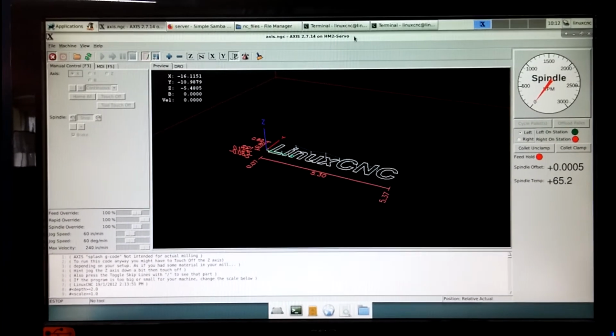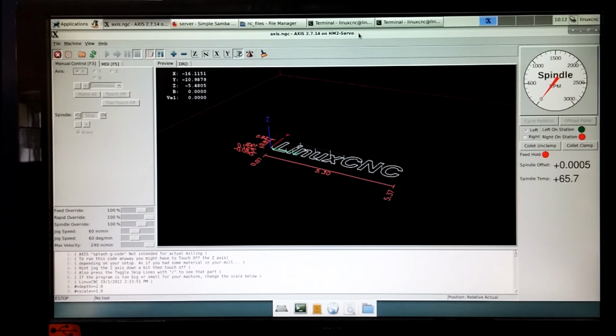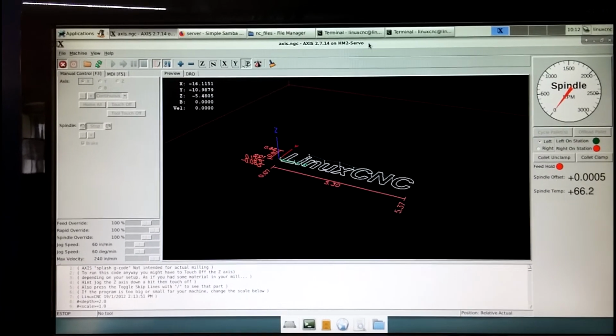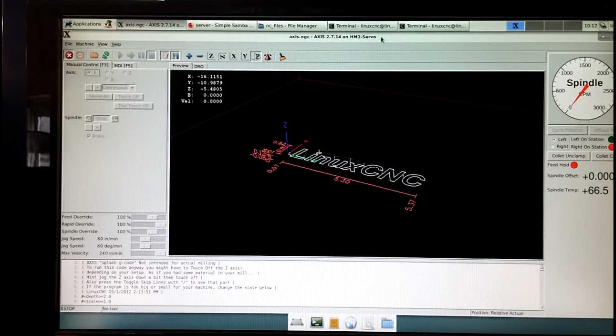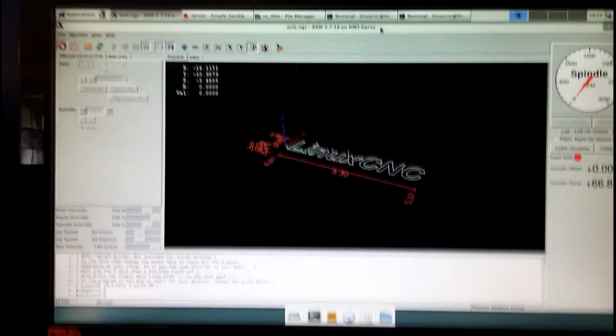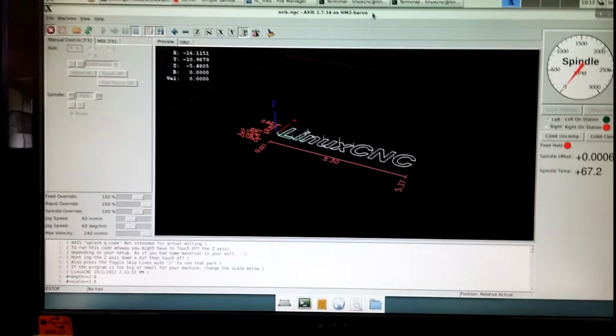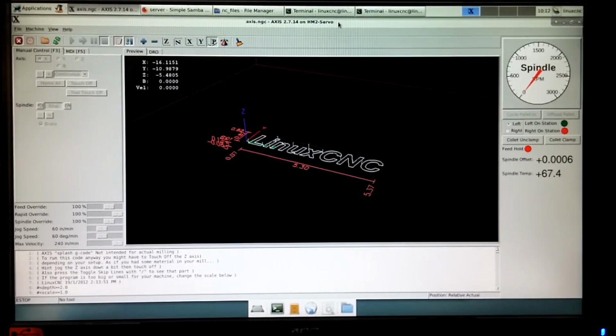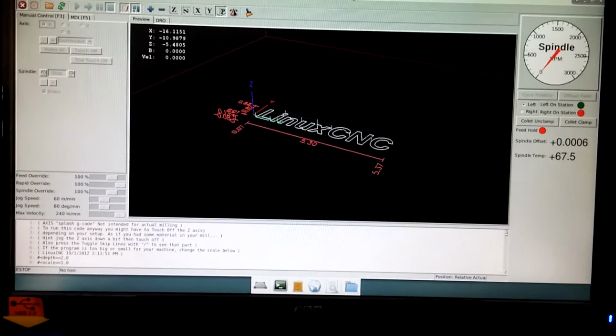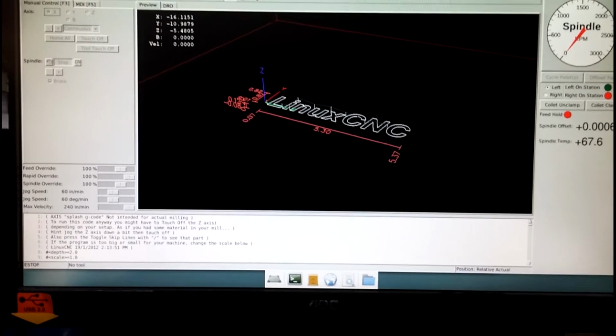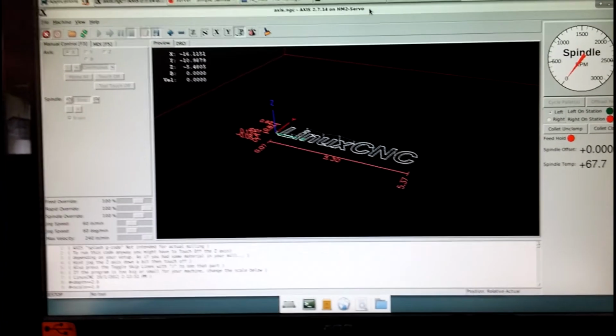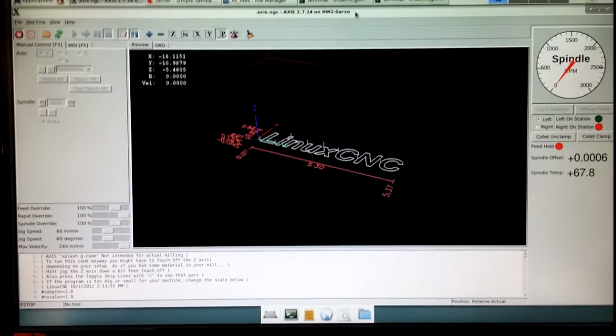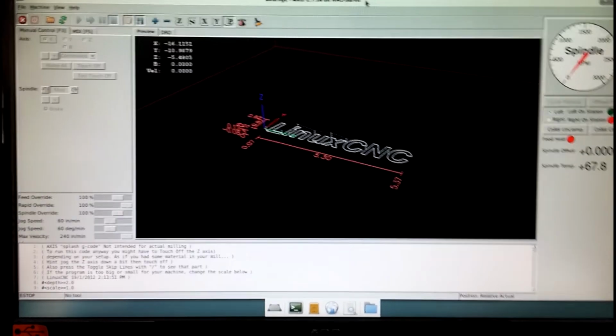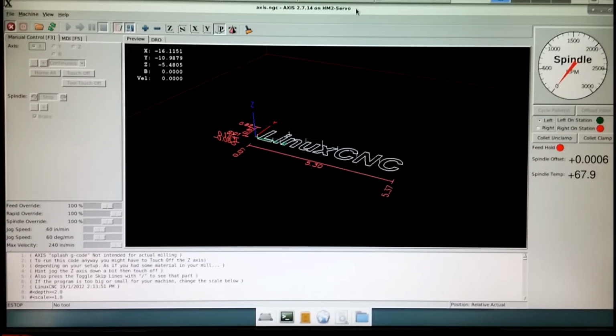The e-stop loop on this machine is hardwired. When you hit the e-stop, any of the mushroom switches, it kills power to the VFD, the hydraulics, the servo drives, among other things. So the computer isn't controlling, or in control of, that.